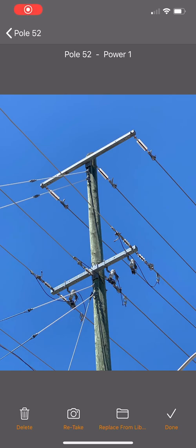The crossarm attachment. Now you'll notice in this pull shot we have two crossarms. Both are dead ending. The lower crossarm continues on through, and the primaries are a lower value going through. The ones coming from the north are 556s, and the ones going south are 336s. You'll also notice on that same crossarm that we have three primary fuses, and those lines are anchored.